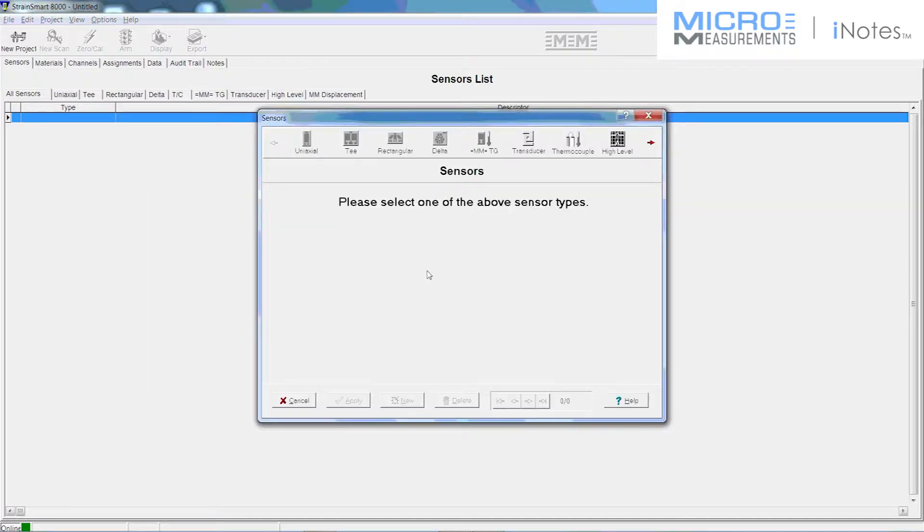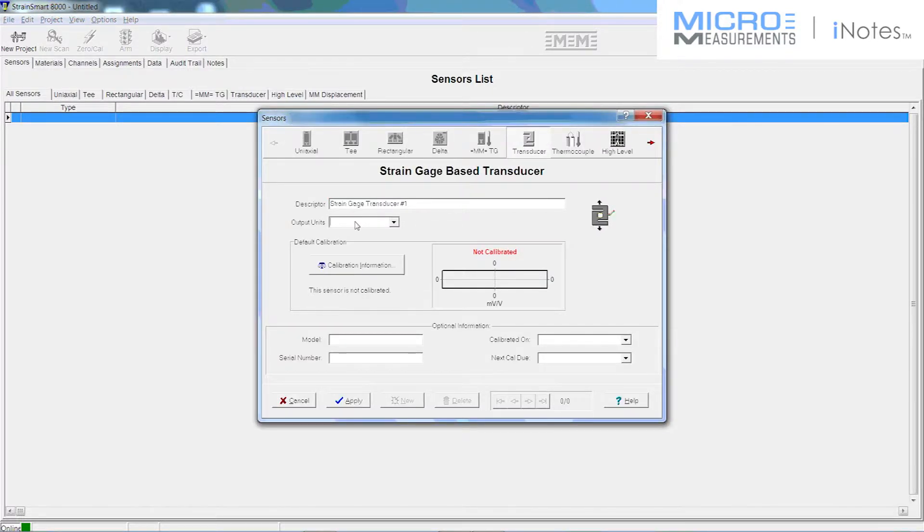I'm now going to set up our input using System 8000 and our StrainSmart software. And I want to put this in as a calibrated transducer. I'm going to create a new sensor. In this case a transducer. And I'm going to use Newton meters as my output units. But I'm not going to put in any calibration information at this point. We're going to do that by putting a known input into our transducer.